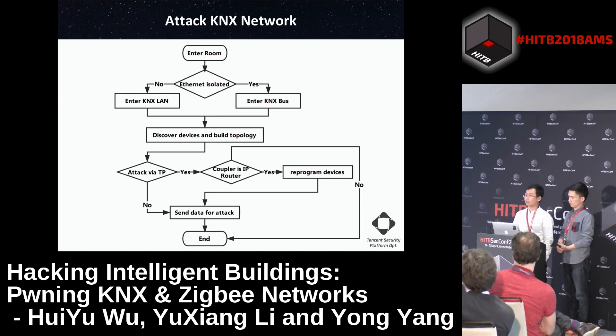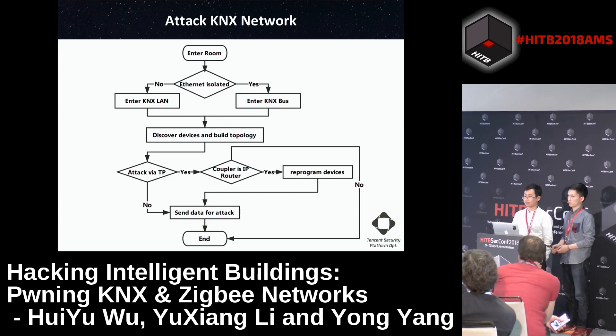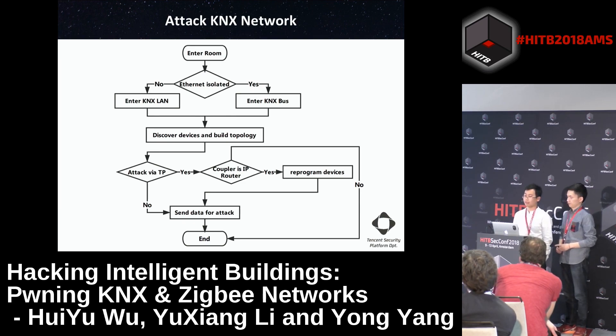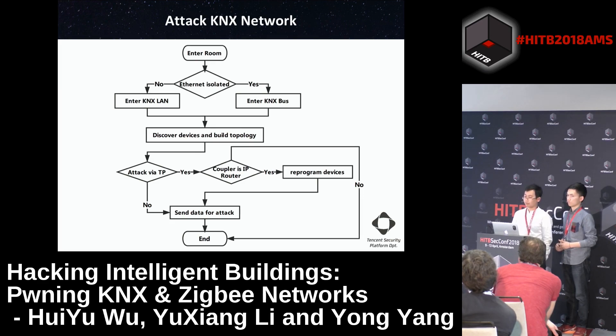This is the general process of attacking the KNX network. The first step is to determine whether the Ethernet network is isolated. If not, we can enter the LAN by cracking it. After entering the LAN, we discover devices, build topologies, and finally send data for the attack. If the Ethernet is isolated, we need to enter the KNX bus physically, discover devices, build topologies. If we find the couplers are IP routers, we can reprogram devices including modifying coupler network configurations, and finally send data for attack.